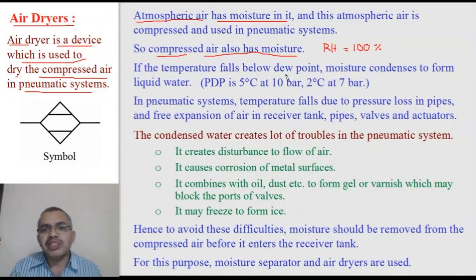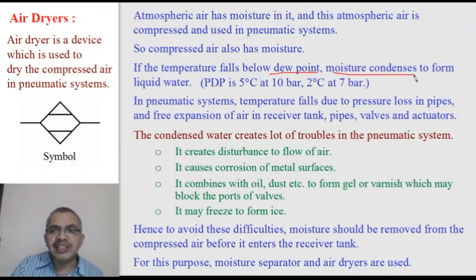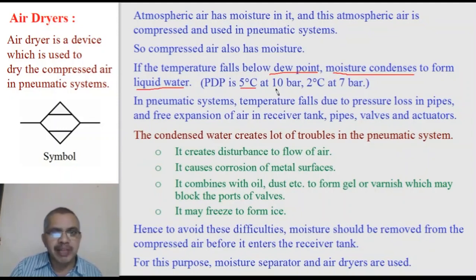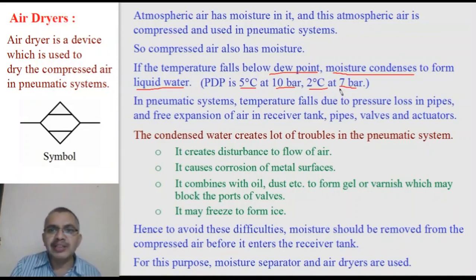The problem with moisture in compressed air is that if the temperature of the compressed air falls below the pressure dew point, the moisture condenses into liquid water. The pressure dew point is nearly 5°C at 10 bar pressure. If the pressure is 7 bar, then the pressure dew point is 2°C. That means if compressed air at 10 bar is cooled to 5°C, moisture will condense into liquid water.